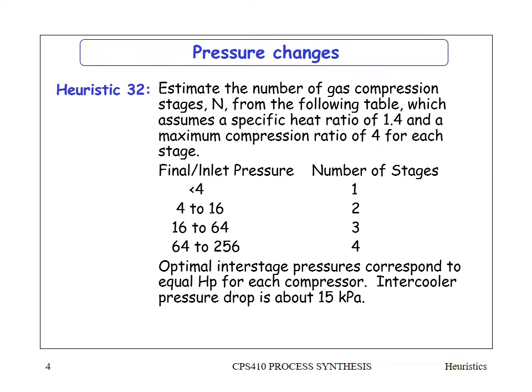Generally, with a one-to-256 bar compressor using four stages, each stage uses the same amount of power provided the pressure ratio is equal across stages — so going from one to four bar uses the same power as going from four to 16 bar, and so forth. The intercooler pressure drop is about 15 kPa, which is relatively small, but it illustrates that you need an intercooler between stages — and that is the whole idea of having separate stages.